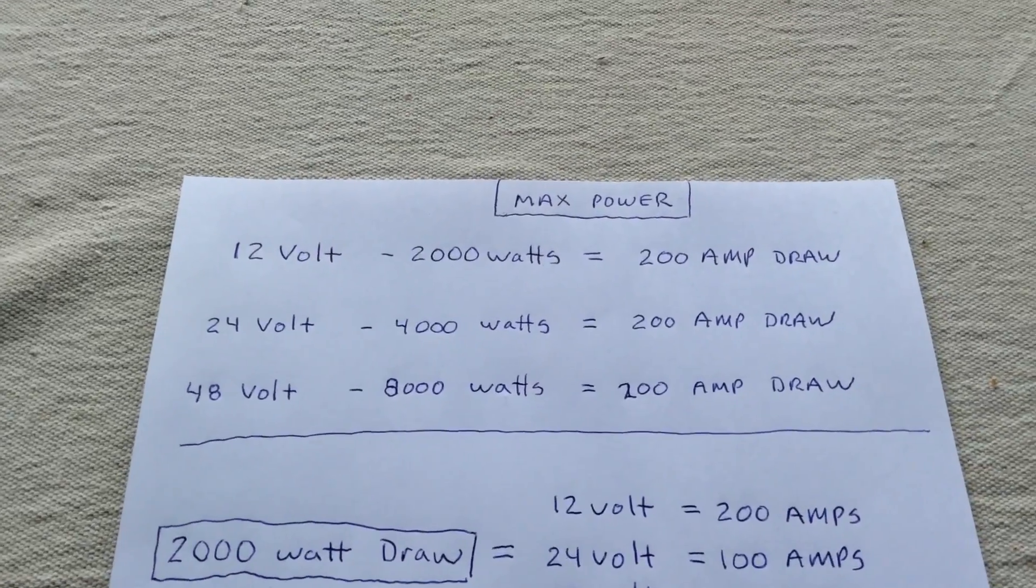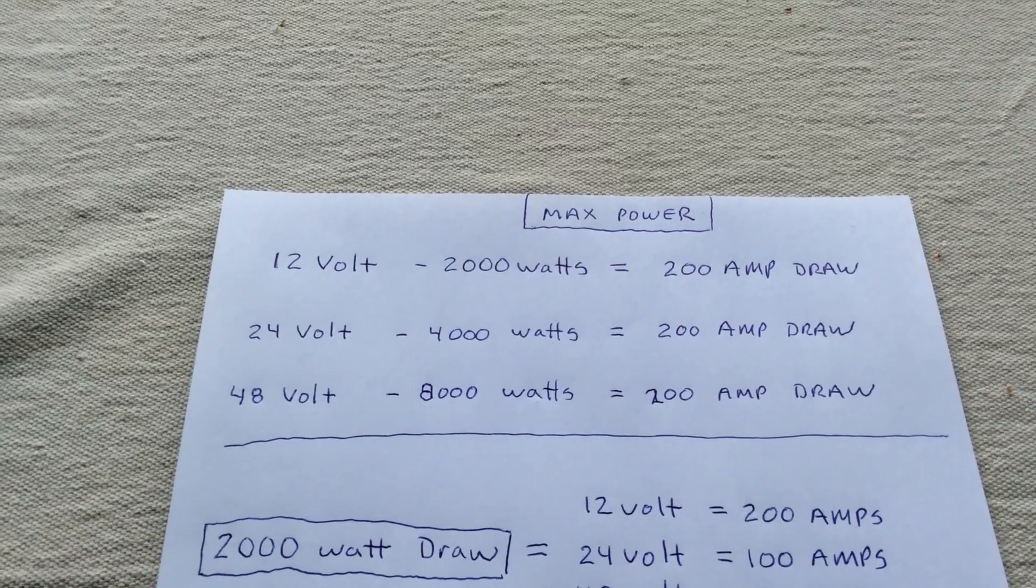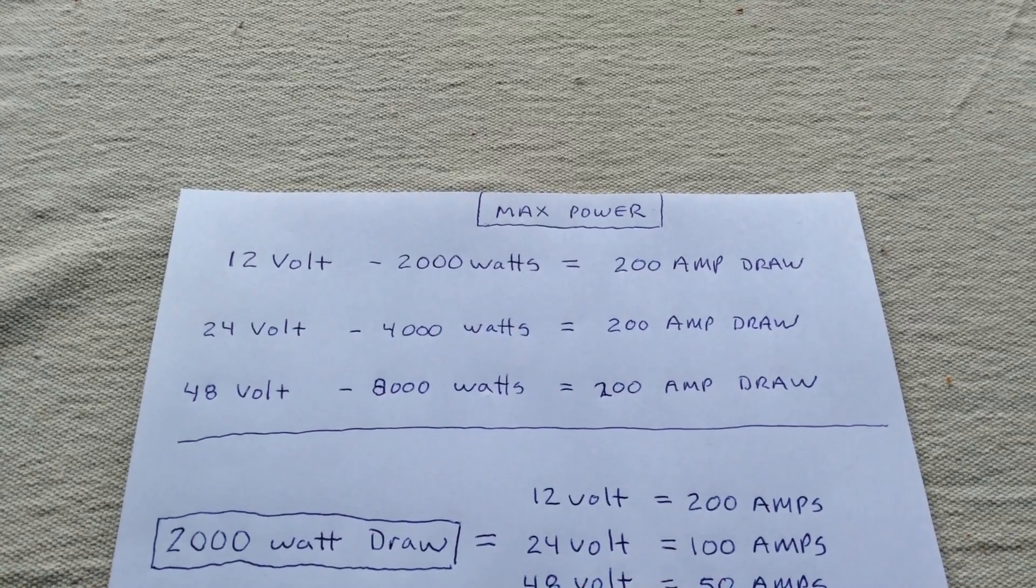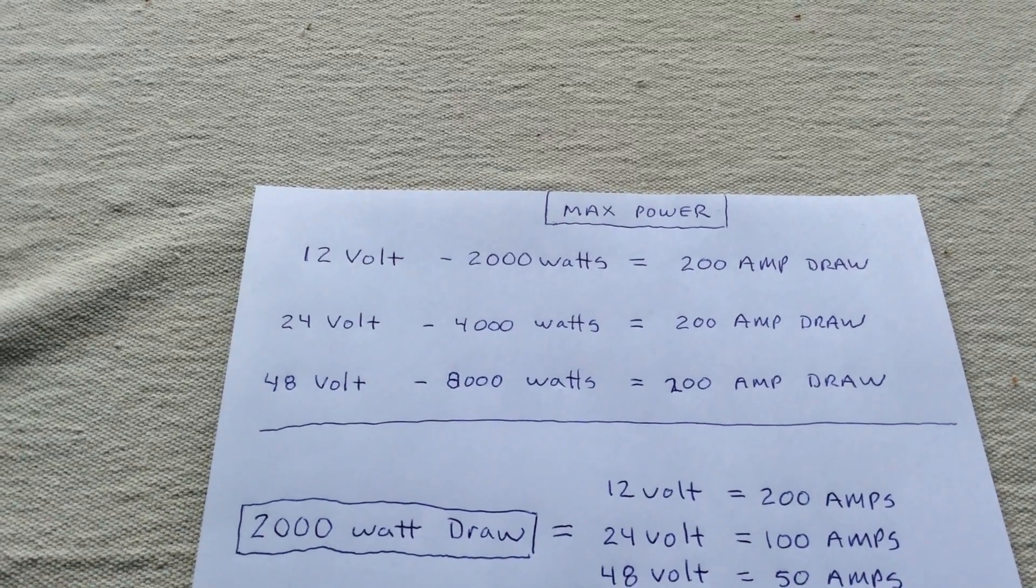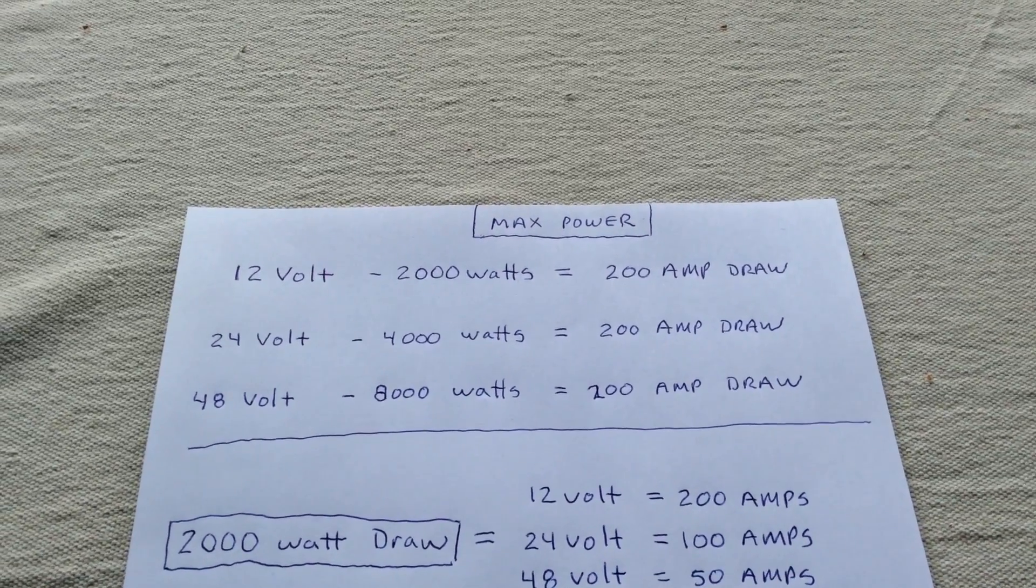Here's my 12 volt system. At 2,000 watts, you're going to draw 200 amps. Now if I have a 24 volt system with the same battery bank, I can go 4,000 watts to draw the same 200 amps. And then your large system is 48 volt. I can go 8,000 watts and draw 200 amps.